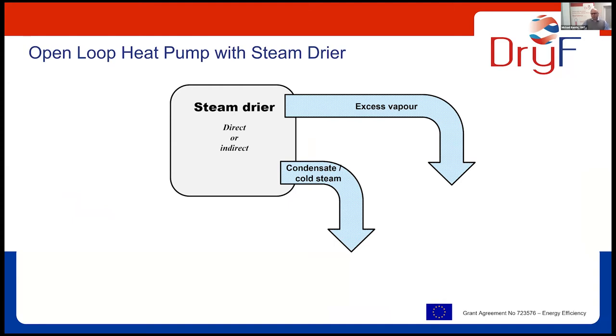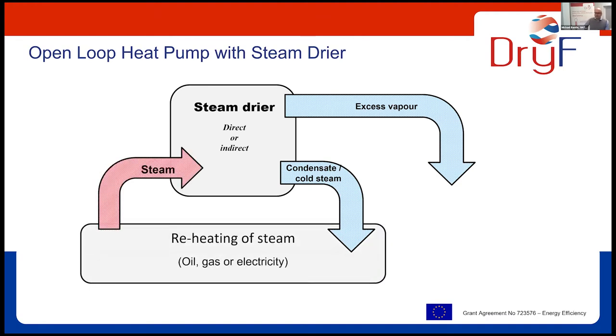A steam dryer, either direct or indirect, is what we basically require as a core process for our integration of the open loop. From this steam dryer, we get basically excess vapor, that's basically the water we evaporate from the product. At the same time, also out of the dryer comes, apart from the dry product, a sort of either condensate or a cold steam, which is no longer usable in the drying process simply because of the temperature level.